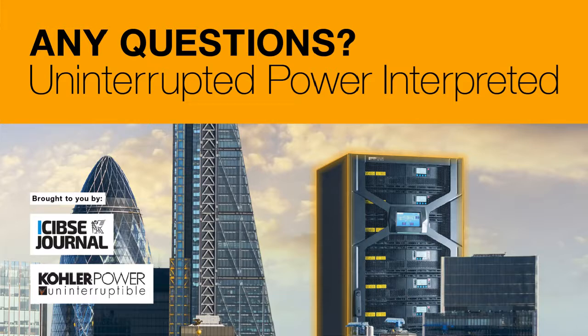As far as maintenance goes, with anything, it's good to regularly exercise the manual bypass, the breakers, and the UPS. Is it absolutely necessary to go to maintenance bypass? It's not absolutely necessary, providing you have a redundant system. But it is very important that we carry out maintenance and regularly exercise the UPS and its surrounding parts. Unfortunately, we see a lot of customers saying, don't touch anything, just come and have a look.